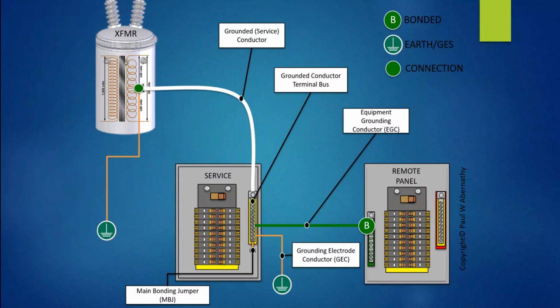So, we'll look at it in this graphic. Let's look at an overview here. Here's your transformer. Here's the grounded conductor. Here it comes to this one common bus where we're going to bring everything. All of our grounded conductors, we're going to bring our equipment grounding conductors all here, just like you'd see in a normal panel. 20 circuits here, 20 circuit breakers. Everything's good. This panel downstream is a remote distribution panel here on the right.